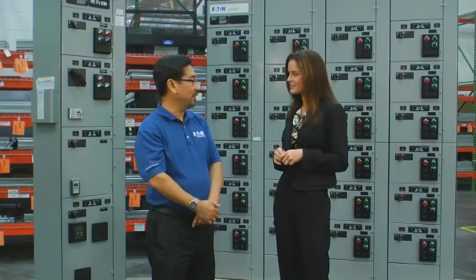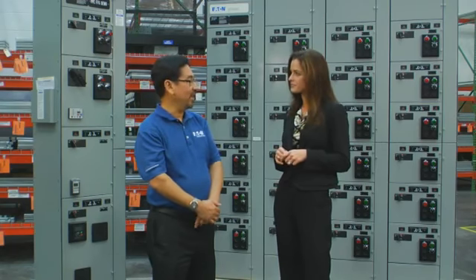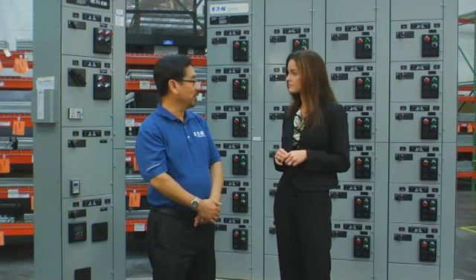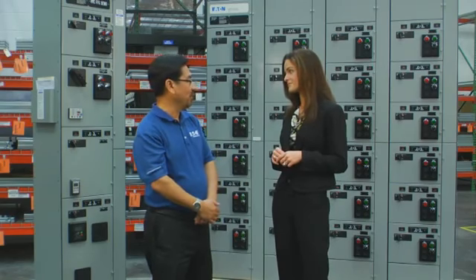Definitely. FlashGard MCC incorporates many of the finest features and innovations that Eaton has introduced in their other arc-resistant product lines throughout the years. But in the end, it boils down to two words: prevention and protection. Prevention is the foundation of arc flash safety, and we've addressed that from several different angles in the design of our cabinet interior. For one thing, FlashGard reduces the possibility of arcing faults that can be triggered from a phase-to-phase or phase-to-ground short circuit. We do that by insulating the entire length of the horizontal bus and providing labyrinth barriers that form a clamshell layer of insulation around the vertical bus.